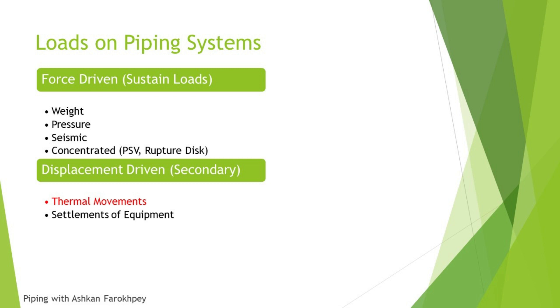And the fourth category that is much more complicated than the other three mentioned loads is concentrated loads. This category is related to forces that come from, for example, PSVs or rupture discs. As you know, these kinds of equipment may have some sudden movements, and in these sudden movements some forces are applied to our piping system. So we have to prepare the restraints and supports of our system to control these sudden loads on our piping.